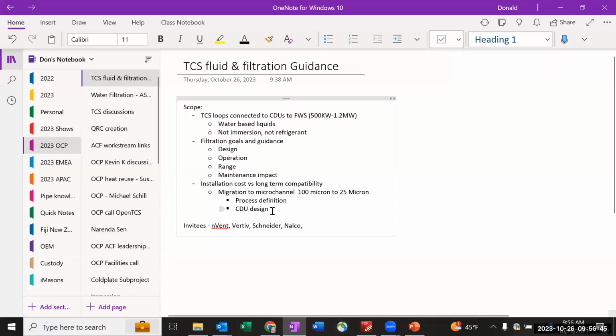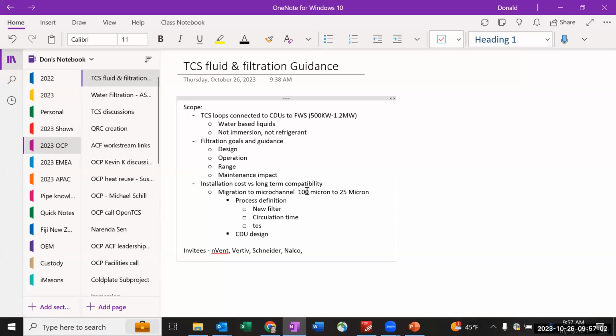There's testing that can be done to validate that the fluid is at an acceptable level, whether it takes days or hours, and then the coolant is at 25 microns. It's safe to allow the coolant to go through a microchannel cold plate. Now you can put your new server in and you're good to go.